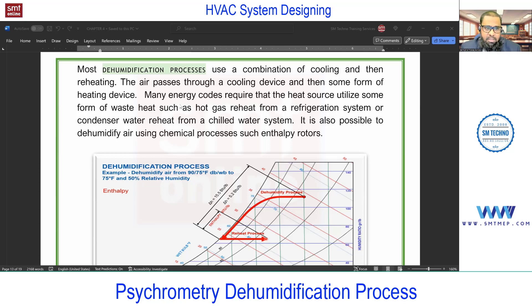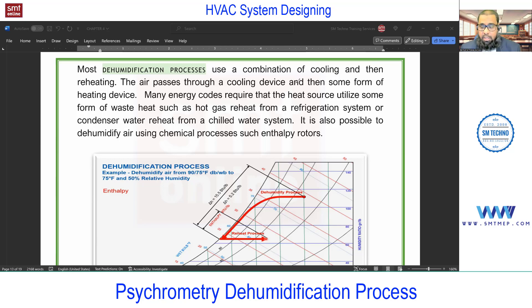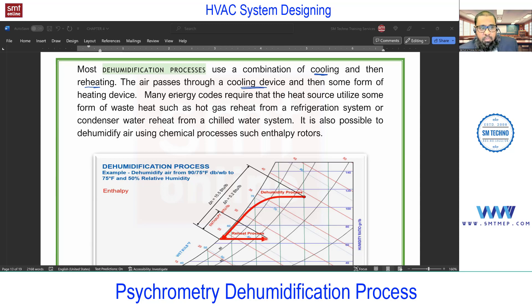The dehumidification process exactly is dehumidification with the reheat coil. Most dehumidification processes use a combination of cooling and then reheating. This is not in all cases, but for normal window or split systems you will find only cooling — no reheating coil. But precisely, if you want to maintain humidity, two coils are required: one cooling coil and one reheating coil. Air passes through a cooling device (the cooling coil) then through some form of heating device (the heating coil), and this heat can be utilized from waste heat energy from the system — from the condenser in the vapor compression cycle.